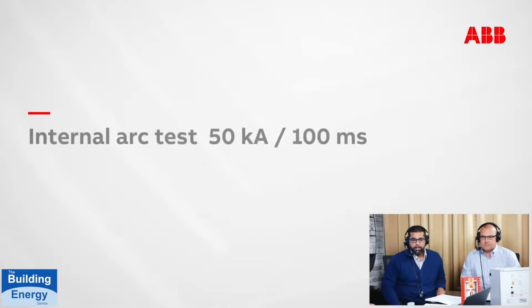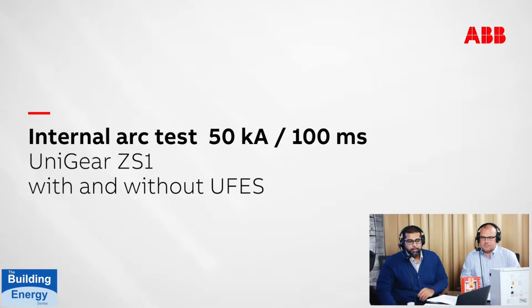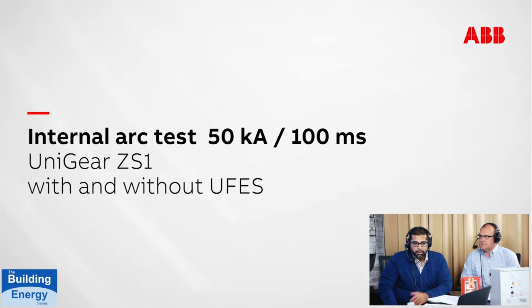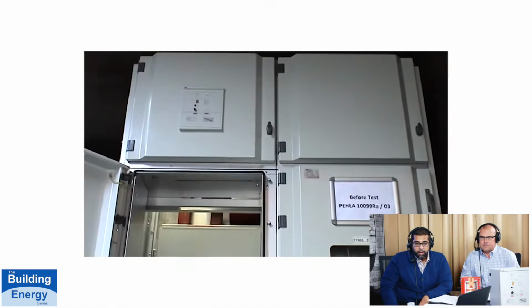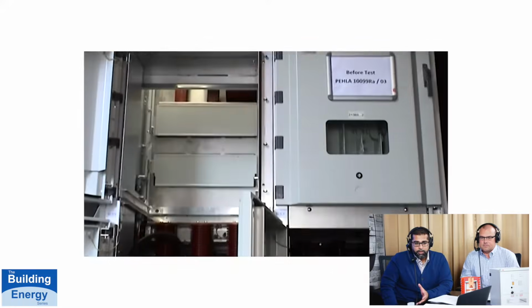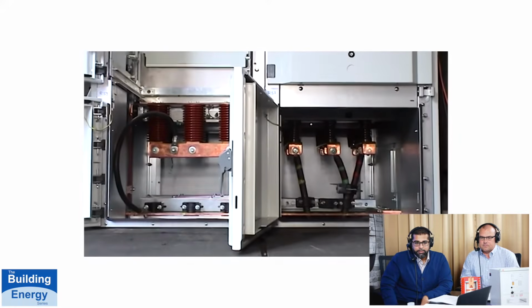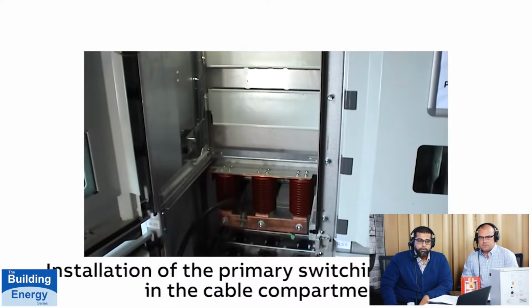That's right. So, getting into the equipment side, you touched on it a little bit as well. This was a test that we conducted inside ABB at 50 kiloamps for 100 milliseconds only, between switchgear that has the ultra-fast earthing switch installed and that which doesn't. It shows you the amount of destruction that can take place inside your switchgear within just a matter of 100 milliseconds.